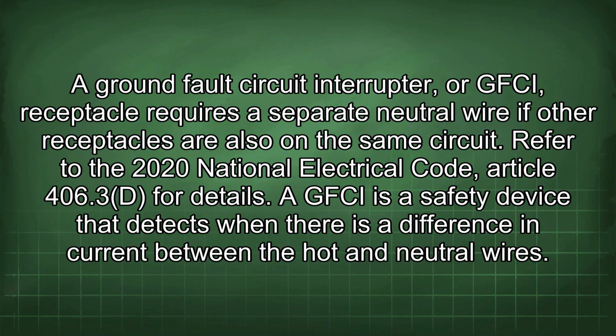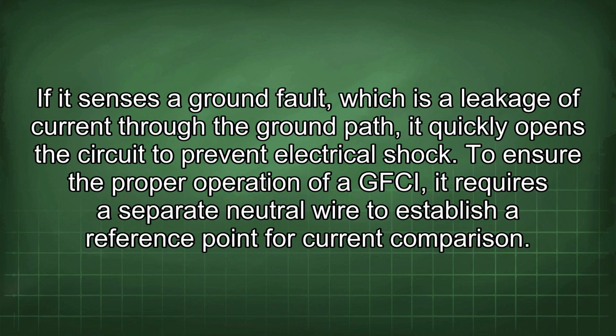A ground fault circuit interrupter, or GFCI, receptacle requires a separate neutral wire if other receptacles are also on the same circuit. Refer to the 2020 National Electrical Code, Article 406.3(D) for details. A GFCI is a safety device that detects when there is a difference in current between the hot and neutral wires. If it senses a ground fault, which is a leakage of current through the ground path, it quickly opens the circuit to prevent electrical shock.